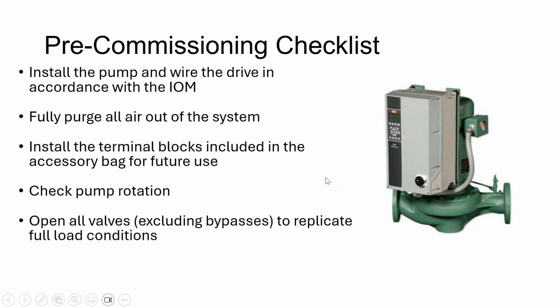And then when you go to start it up, you have to open all the valves, excluding bypasses, to replicate full load conditions. So let's think about this a little bit, right? We order our pumps with this drive based on a flow and head, similar to a regular one without the drive. I'm going to make up some numbers: 300 GPM at 50 feet. So that's what you order it at. Well, we want to make sure that the system is running close to that 300 as maximum flow, full load conditions.